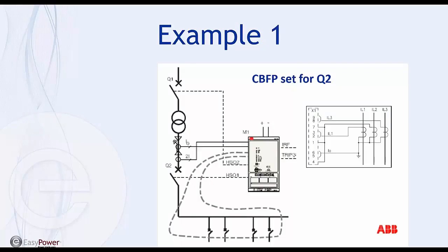Now let's take a look at some examples, and we'll show you how easy it is to configure the switches. Right here you have a main transformer connected to a single bus, and you're using an REA 101 main unit to provide the arc flash protection. You can see here you've got two phases connected to it, and the zero sequence CT for the ground. You're tripping Q2. We're set up for breaker failure to trip Q1. We have a lens sensor that's protecting the bus, the breaker, and the terminations.